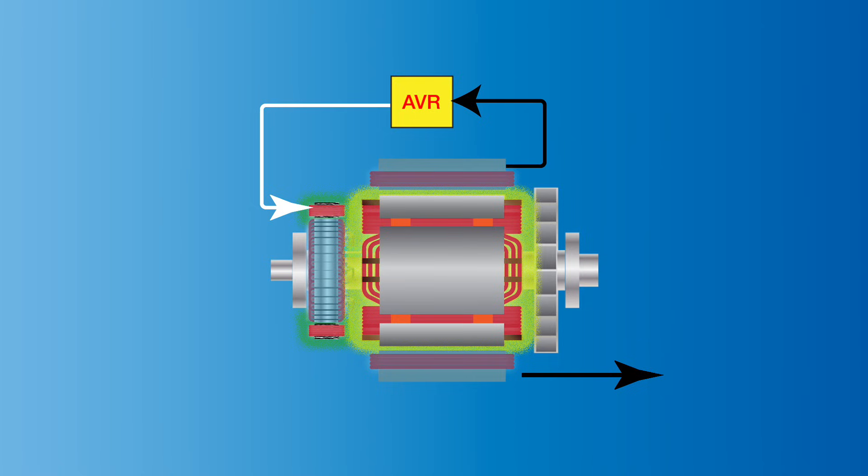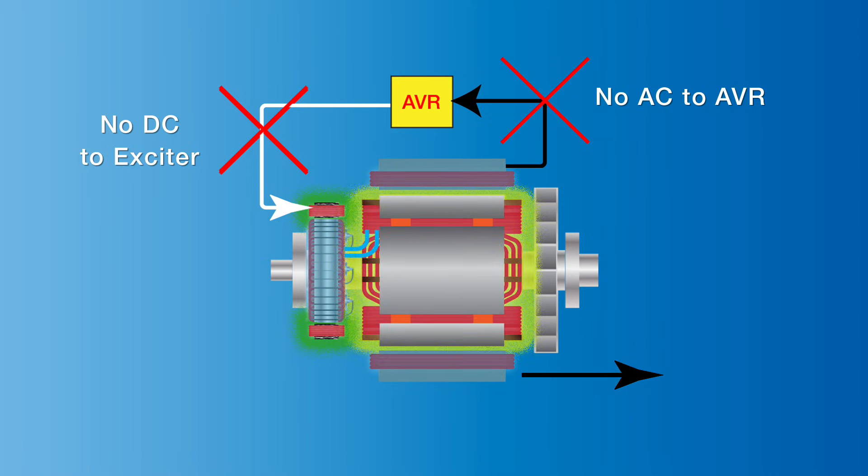However, once the AC reference feed from the stator to the AVR drops to a certain level due to a high percentage of motor starting load causing a severe drop in output voltage when the load is applied, the AVR doesn't receive enough AC input voltage to rectify and feed DC current to the exciter. As such, this causes a collapse in excitation with no DC input to the main rotor causing the rotating magnetic field to collapse and hence no AC power from the generator.